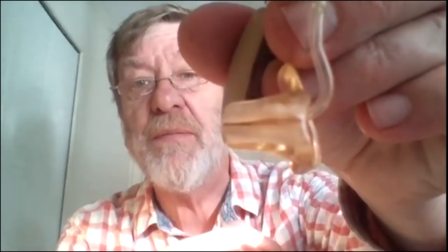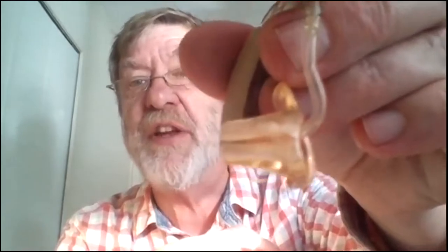So this guy's got less of a hearing loss, and he may experience the occlusion effect. Venting is especially important for people who have good low frequency hearing, okay? Because the occlusion effect is a low frequency phenomenon.